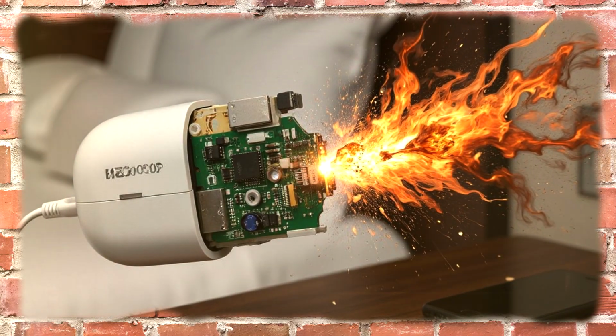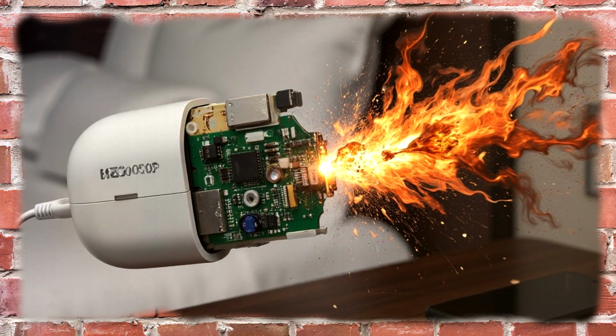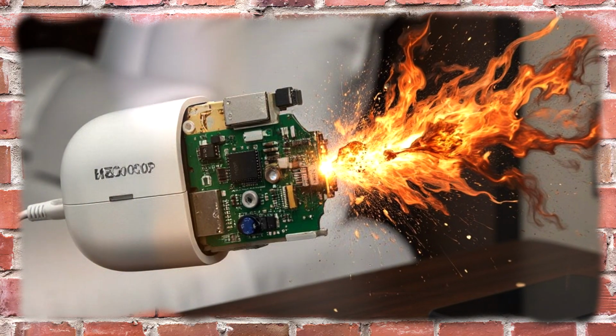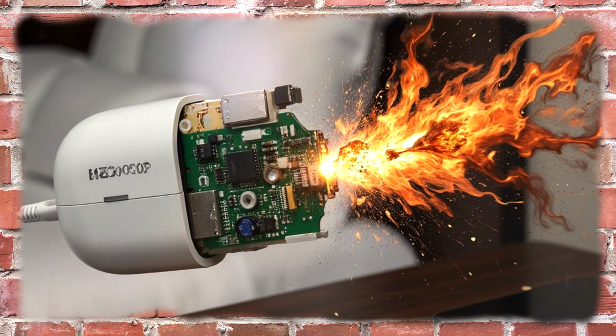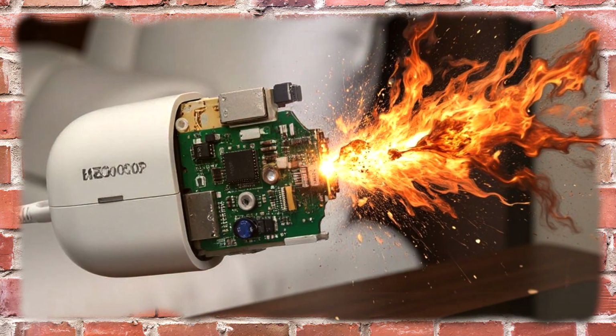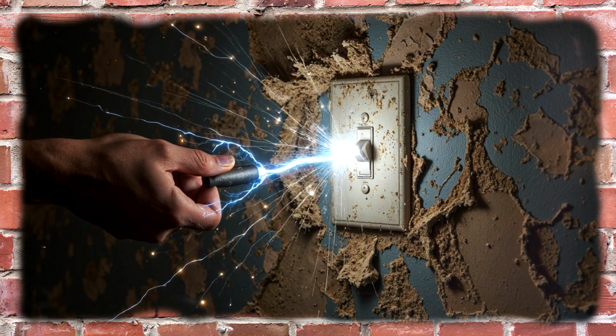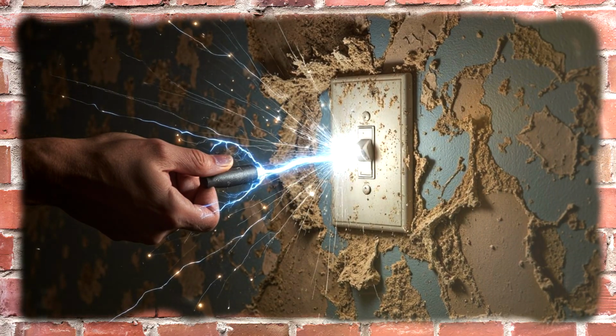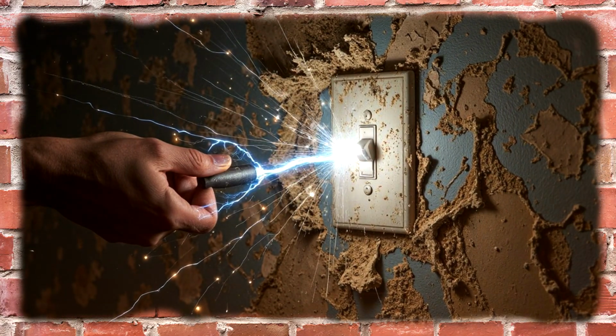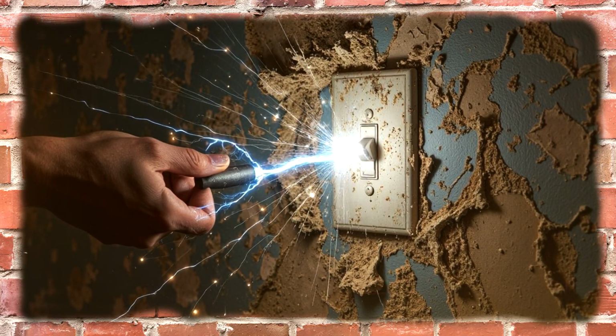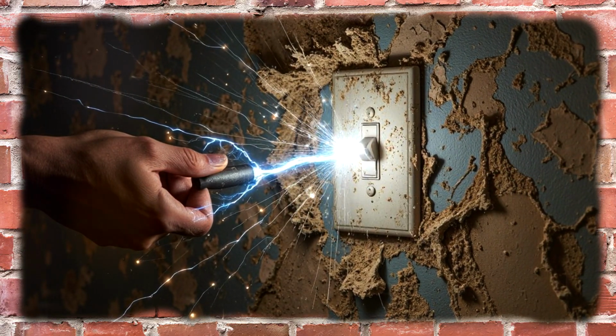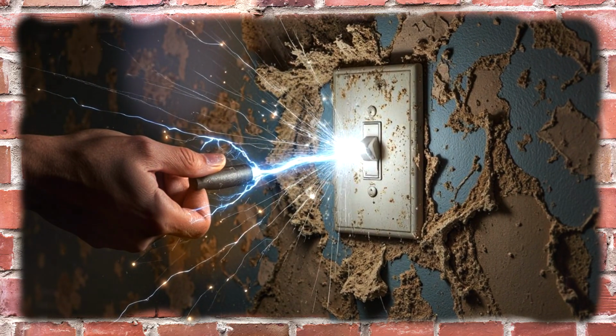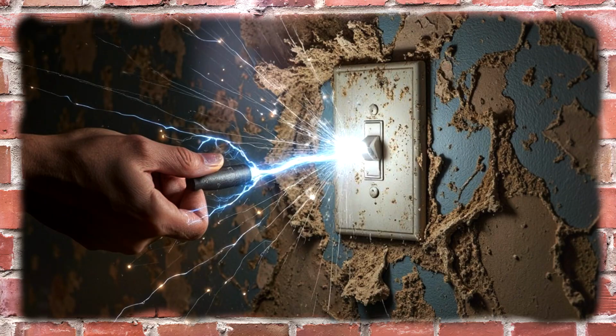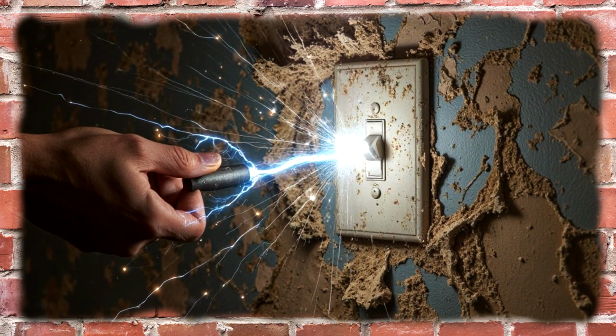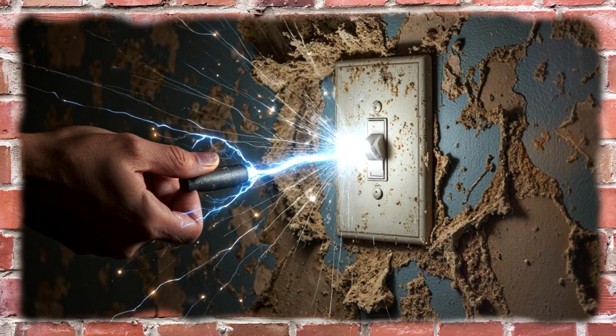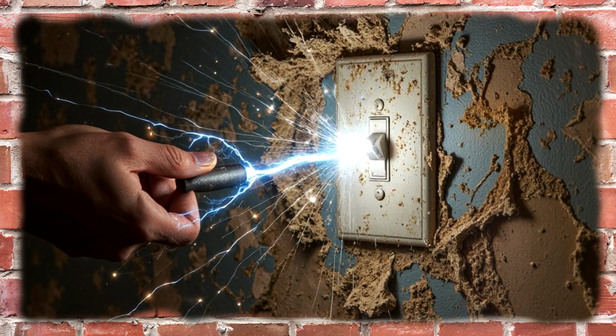Even more perilous is grounding. In the US, the ground wire is often bare, as it shouldn't carry current under normal conditions and is simply attached to metal box parts, whereas in Europe and Russia, grounding is always insulated with a green-yellow sheathing to prevent accidental short circuits during installation. And here arises the question, why such divergence? The answer lies in safety philosophy. In the US, emphasis is placed on circuit breakers and ground fault circuit interrupters, GFCIs, which trip at leakage currents as low as 5 milliamperes. So even if someone touches a bare ground wire, it won't cause a fault.